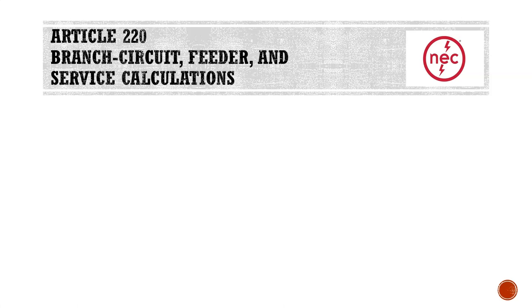Once again, we're going to be in Article 220 — Branch, Circuit, Feeder, and Service Calculations. Article 220 is always where we're going to be going whenever we're trying to calculate any type of service size. It's easy to get Article 220 and 230 confused, because 230 covers services. We have to keep in mind that 230 has general service requirements, such as vertical clearance heights and the number of service disconnect means, whereas 220 is about calculations — in other words, sizing.